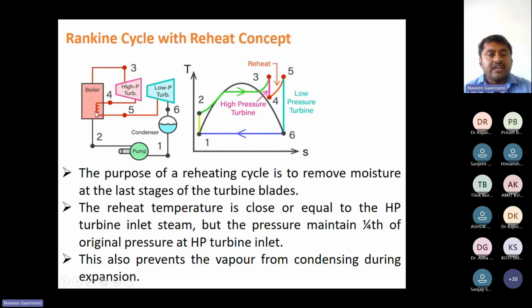It could be heated, and again the output of the reheater is coming to the IP turbine. This is nothing but HRH, hot reheat steam, as per our power plant terminology. In this condition the pressure is more or less the same, but the temperature is raised to 540 degrees, as we have given here, 540. So that temperature is going to the IP turbine.